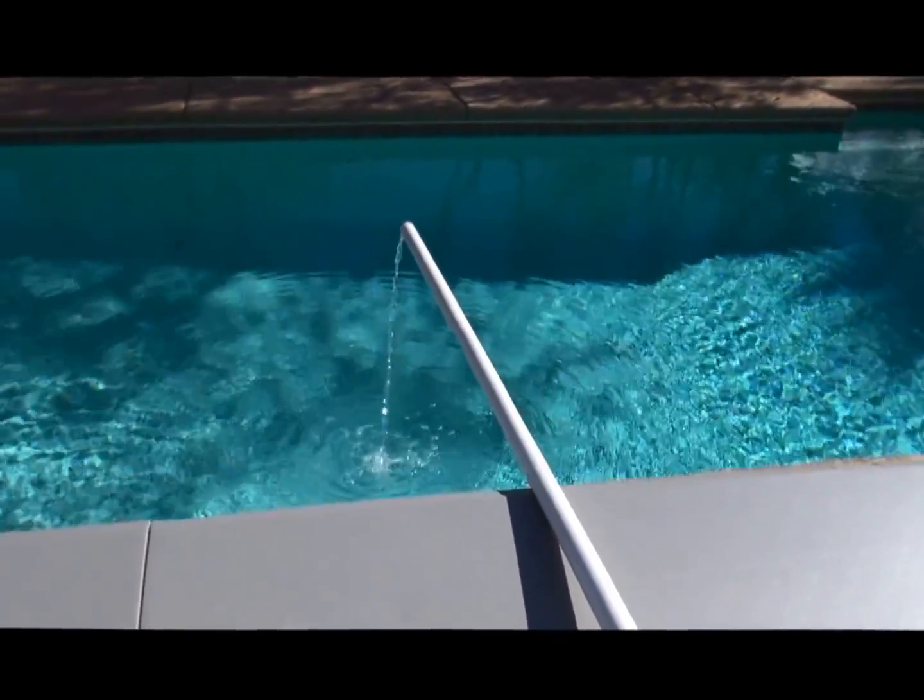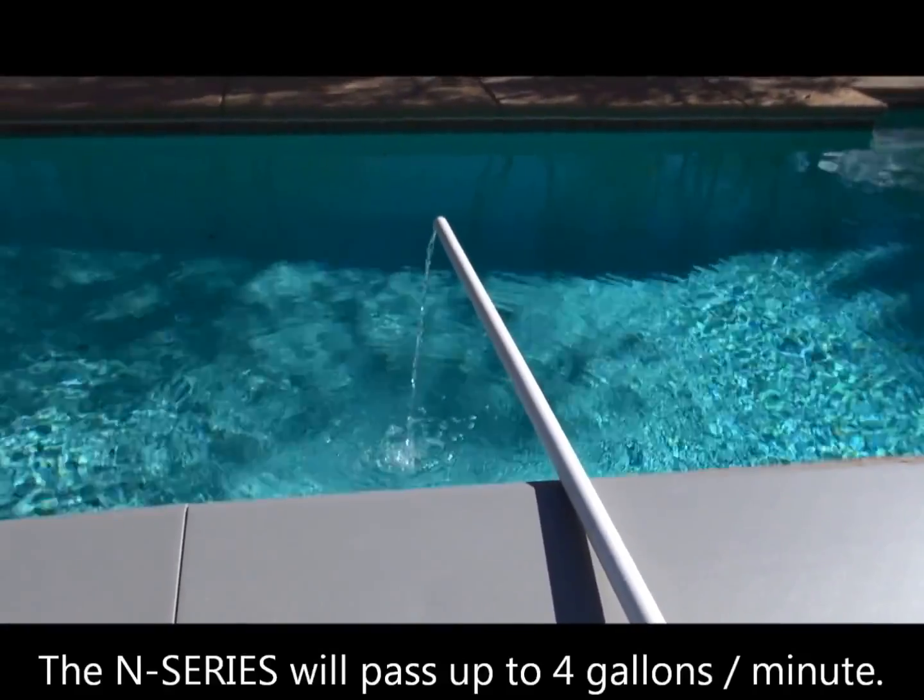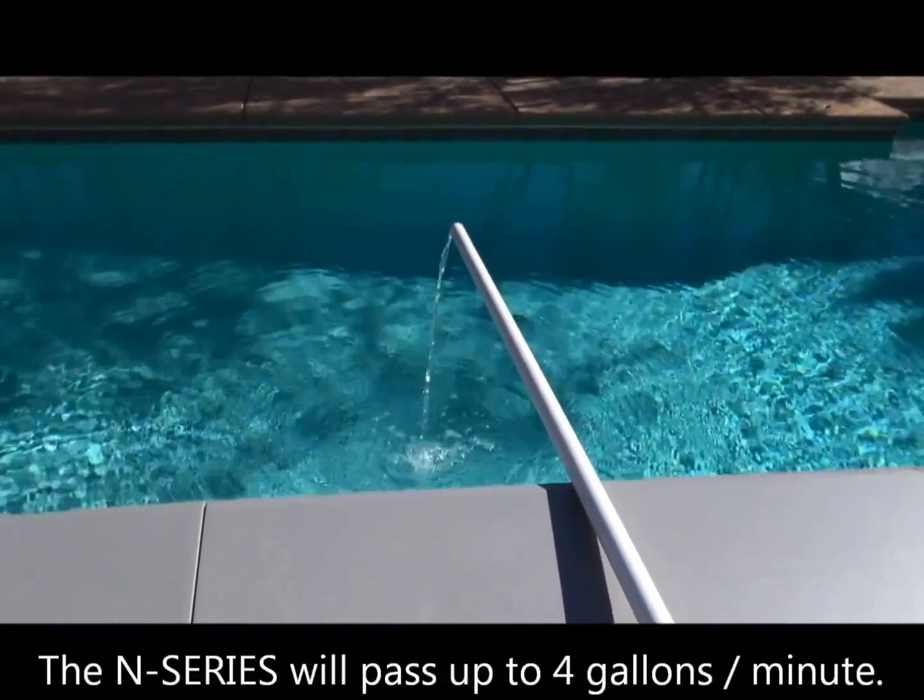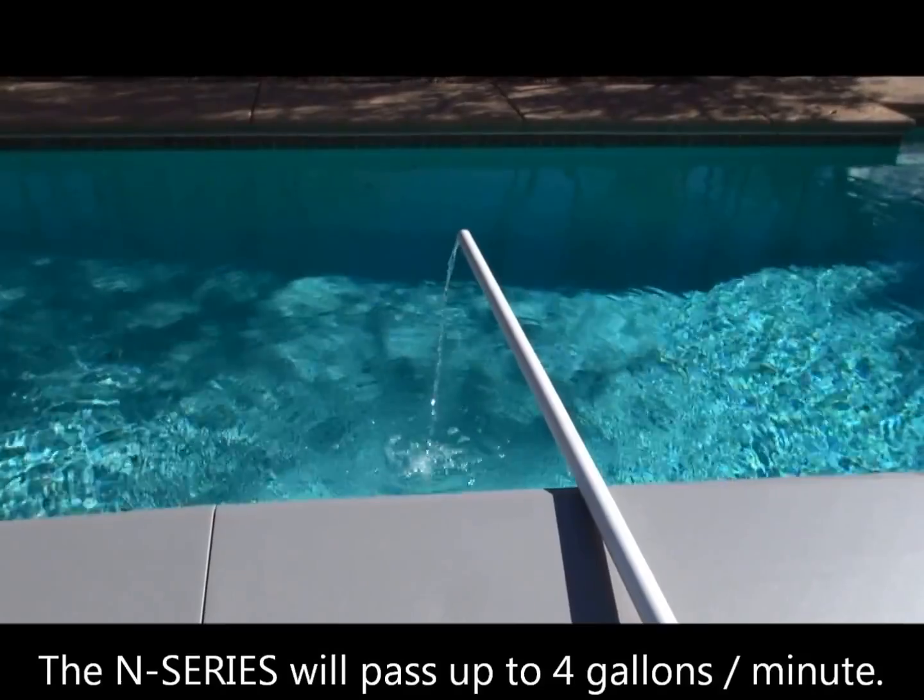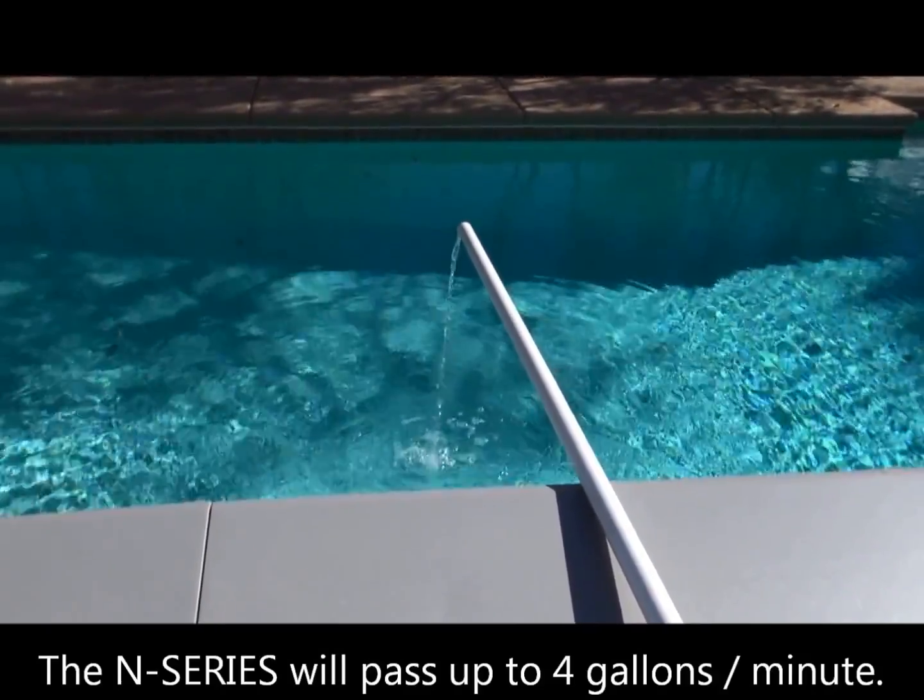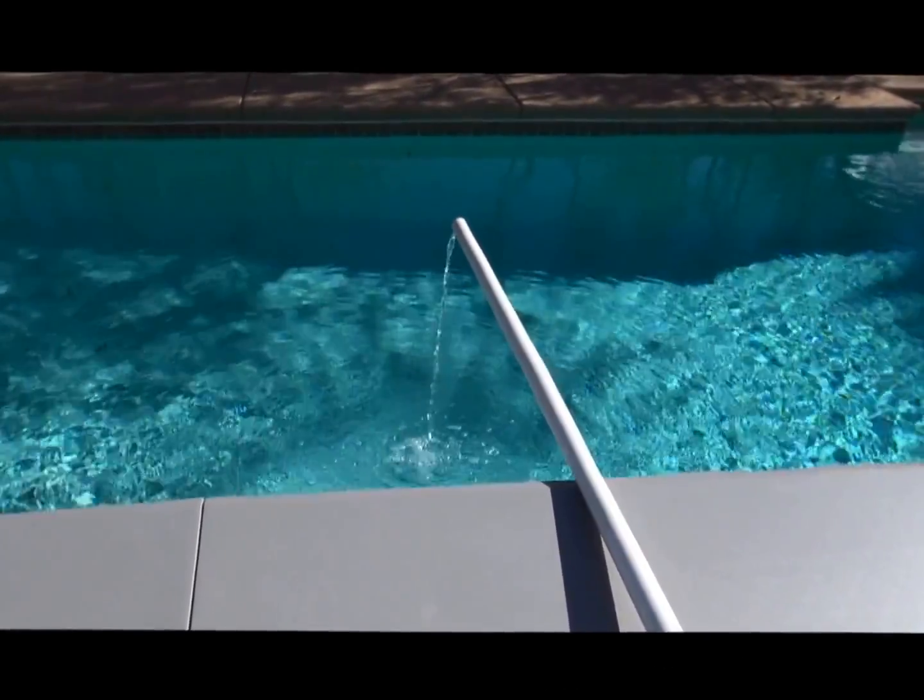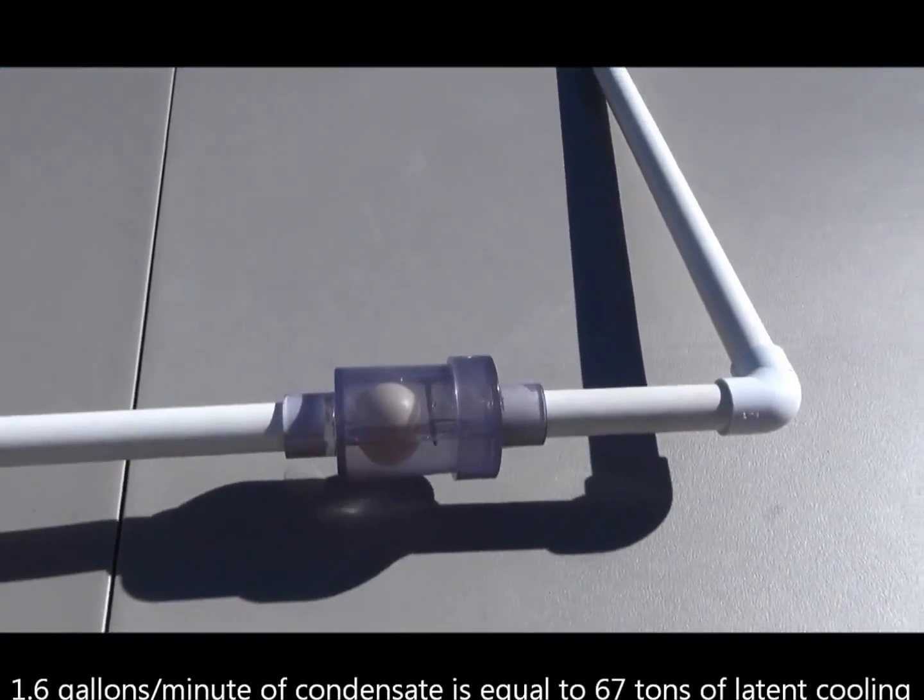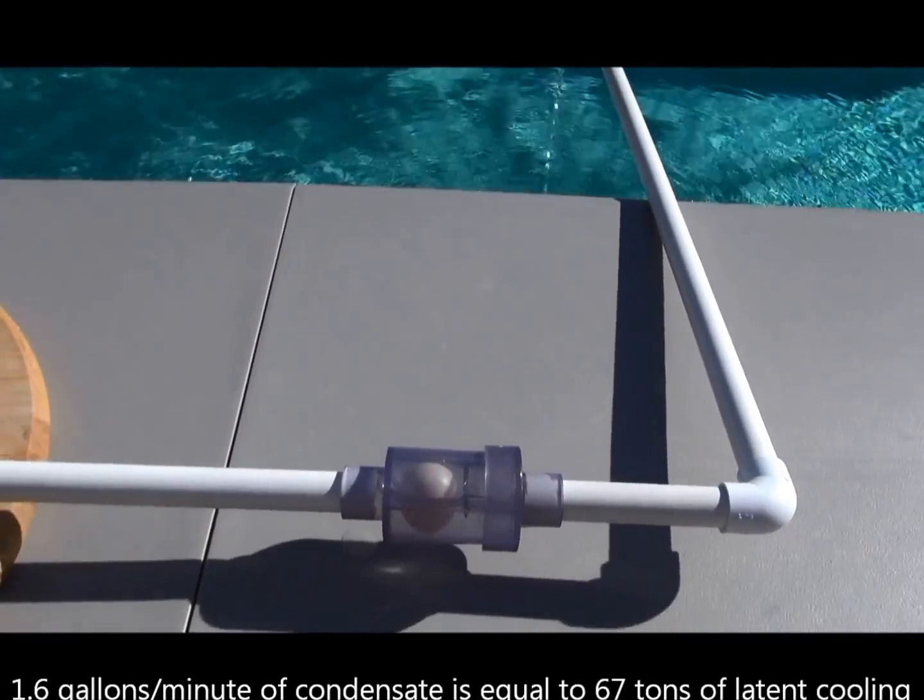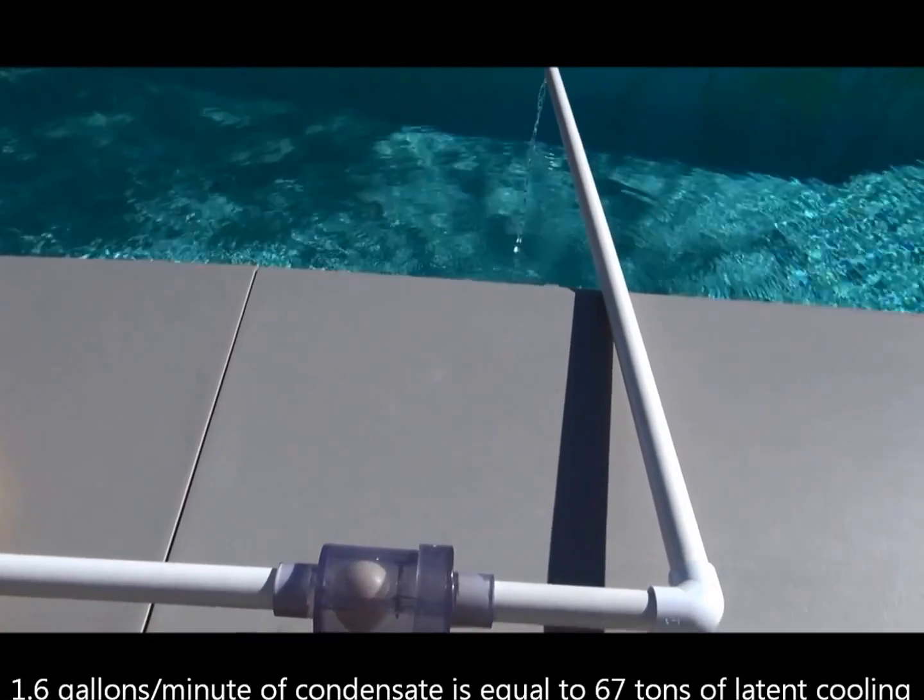This trap will pass 4 gallons per minute, but like I said in the positive display or demonstration, 1.6 gallons per minute is equivalent to 67 tons of latent cooling.